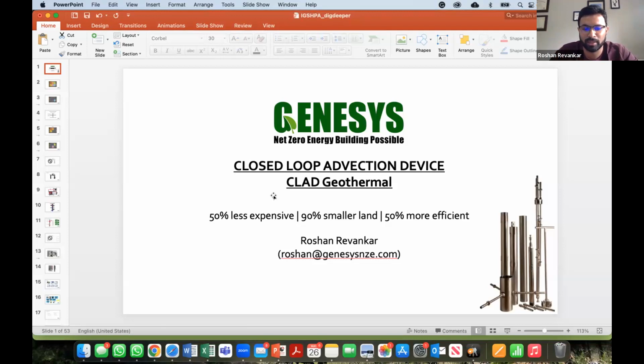We are looking to finish up a hot water heating project right close to Central Park in New York, and there is very little space there. But all they will do is have 3 CLAD units on one side and 1 discharge on the other side of the building. It is a retrofit application. So as long as you can locate the production well close to where the mechanical room is, to avoid piping and disruption, it seems like a very good option to use CLAD.